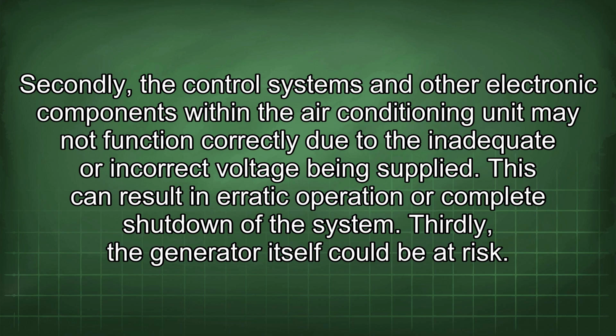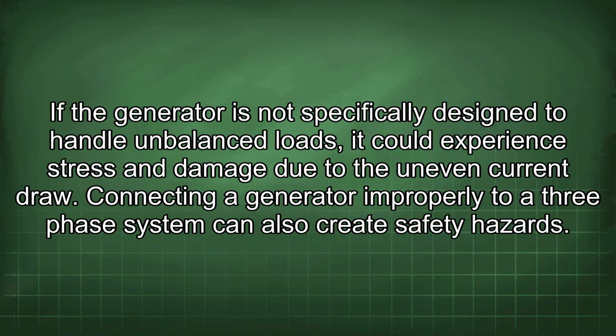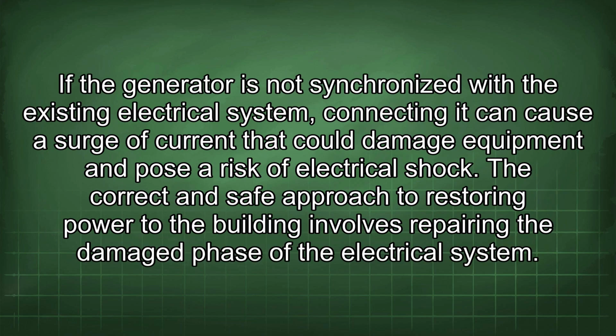Thirdly, the generator itself could be at risk. If the generator is not specifically designed to handle unbalanced loads, it could experience stress and damage due to the uneven current draw. Connecting a generator improperly to a three-phase system can also create safety hazards. If the generator is not synchronized with the existing electrical system it is connecting to, it can cause a surge of current that could damage equipment and pose a risk of electrical shock.